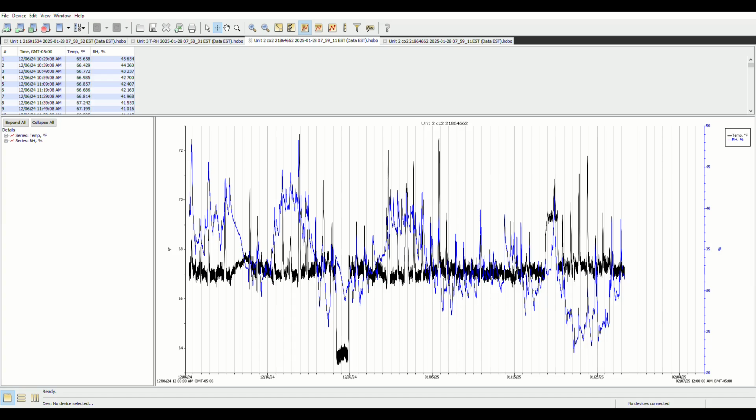Unit 2 was the interior conditions. I wanted to monitor those to see what they were and if they were a contributing factor. He previously had a humidifier in there, which I don't believe has been used because the average relative humidity in the building was somewhere right around 35%, as you can see here. He did have some spikes here and there, which is typical, but typically it's hovering right around 35% relative humidity average.